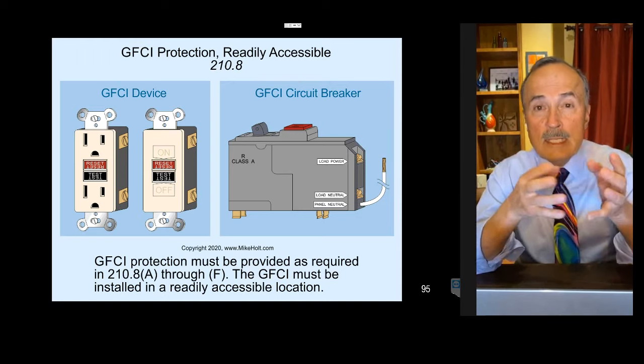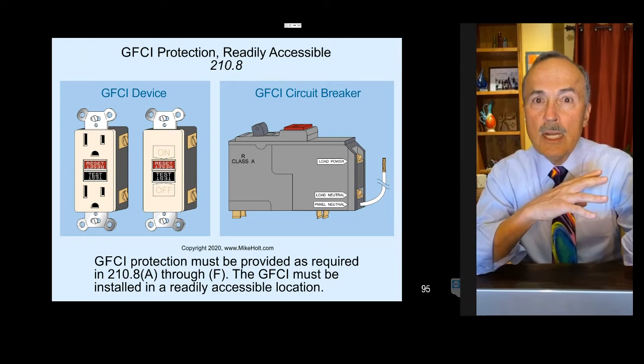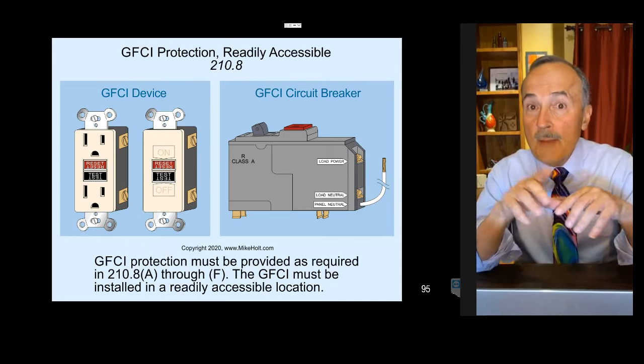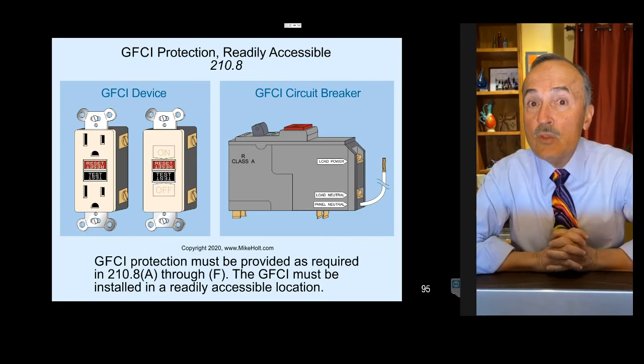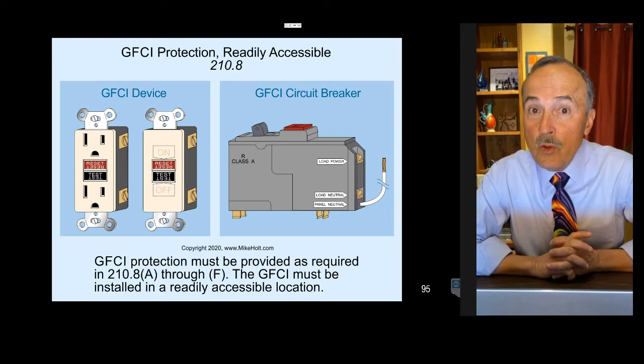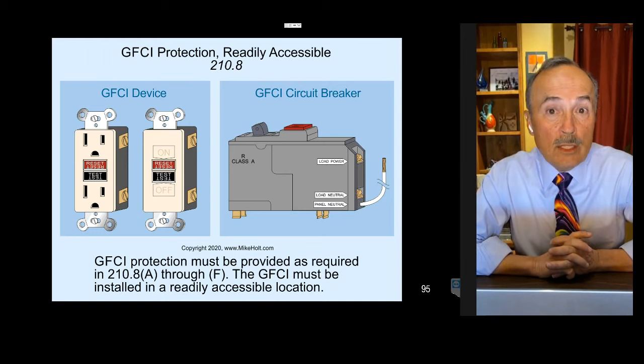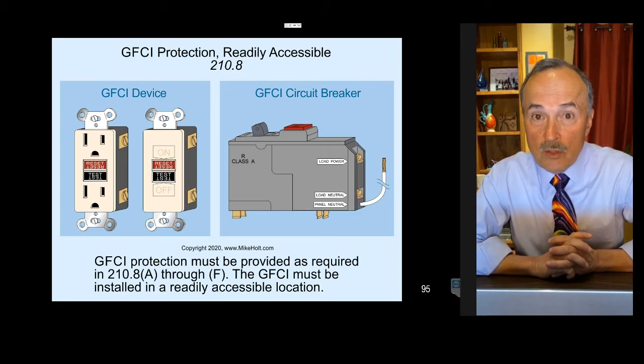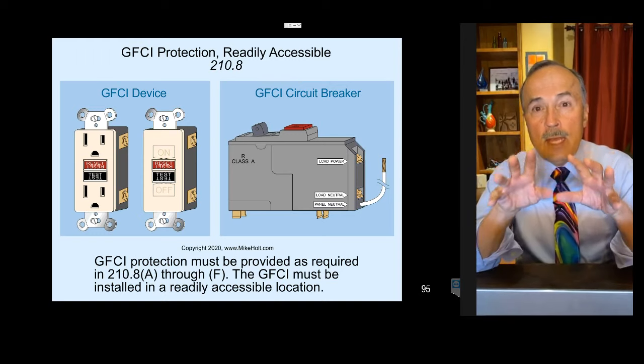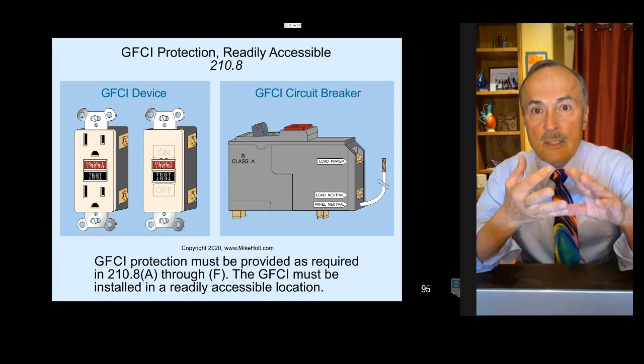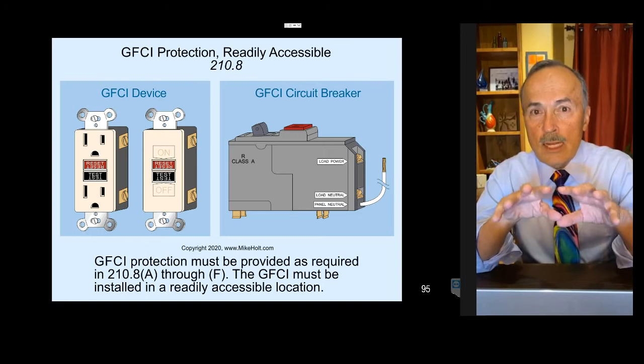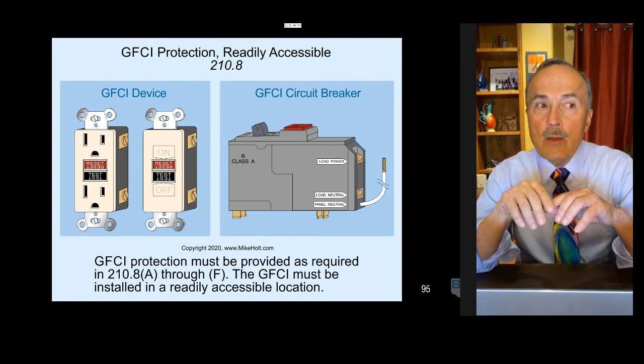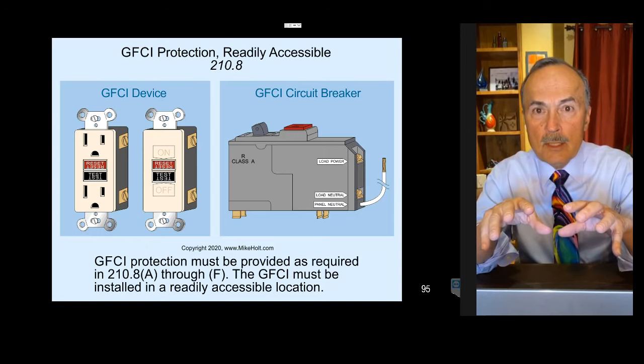You've got to be real careful because GFCIs, as electronic devices, are very sensitive to overvoltage, which is in Article 242 of the 2020 code, having to do with transients from lightning and transients generated from inside the premises. We talk about this in the fundamentals class. And so you've got to be real careful. As a matter of fact, the 2020 code is requiring in dwelling units, the rule is 230.67, that all dwelling unit services have surge protection. That means all new services effectively in the 2020 code and all replacement services.